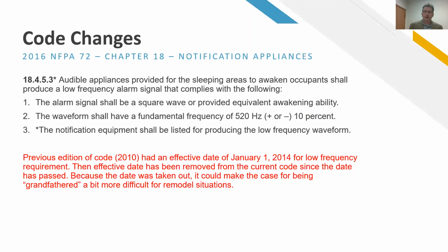So here's a section real quick about audible appliances in sleeping areas. This is generally speaking your hotels, motels, and apartments. If you have notification appliances, you have to have a low frequency sounding device in the sleeping area. That's not low volume, but low frequency is a different type of sound that's more effective in waking people up. Now, the previous edition of the code put a date on it and said effective January 1st, 2014. Well, now we're past that date, so they took the date out of effectiveness, and that does affect your ability to be grandfathered in some cases. So it's definitely something to be aware of, but low frequency is what we have to do now in all sleeping areas. And for anyone listening in a hospital environment, there may also be sleeping rooms for medical staff, and a special kind of notification device needs to be installed in that room.